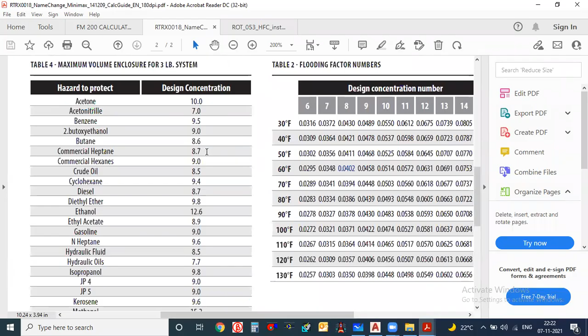The electrical room value is given as 7.5 design concentration. Once you get this 7.5, you have to come to the flooding factor. Here 7.5 is not given, but 8 is given, and the temperature is given in between. Do you have to go for interpolation? No, you don't have to interpolate, just directly go for the higher number, 8. Just understand what temperature you are using.